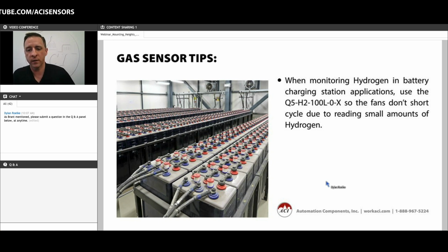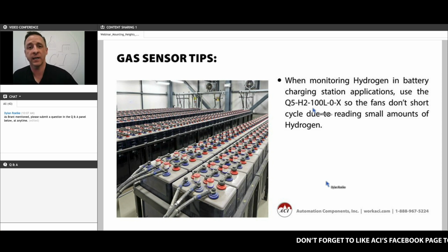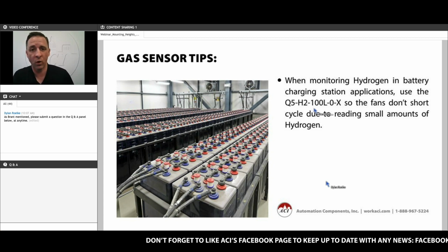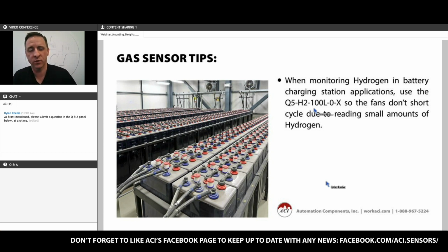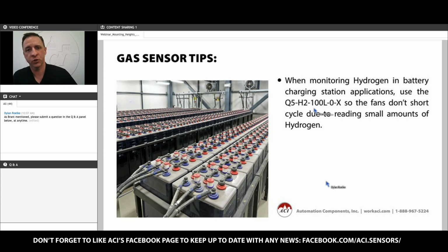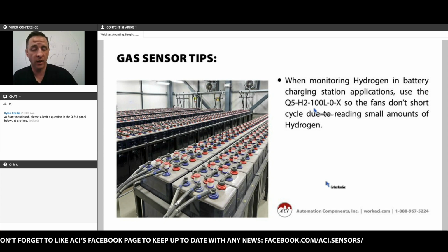So we recommend using a 0 to 100% LEL measurement that would measure from 0 hydrogen in the air all the way up to 100% of the lower explosive limit. That gives you the best coverage and the best detection without short cycling your system and starting your fans too often and wasting energy. There are a number of hydrogen sensors available that have much lower ranges, for example, 0 to 1,000 or 0 to 2,000 parts per million. If you use one of those sensors, because those ranges are so low, they're going to be short cycling your system and you're going to waste energy unnecessarily.